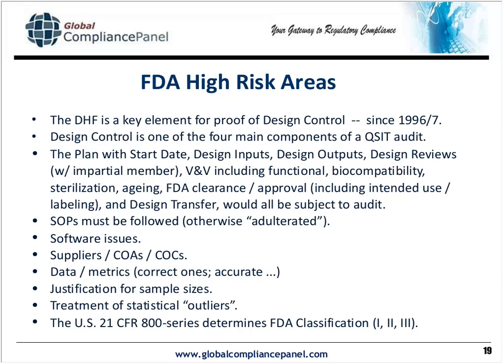Increasingly, the FDA is starting to look at validation to make sure that not only have your requirements been addressed in your test protocols and test cases, but that the data or metrics that you've chosen are the legitimate ones. Even your DOEs can be compromised if you've selected the wrong parameters to measure or control. So again, it's amazing how a very scientific process like statistical process control, design of experiments can be totally undercut by a very unsophisticated, unscientific method of selecting data and metrics.